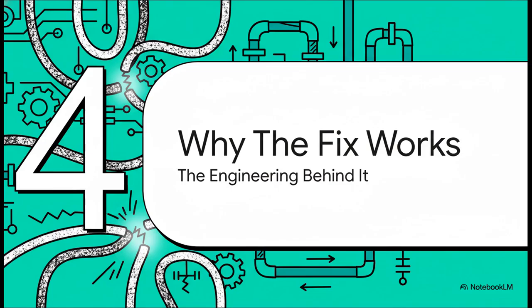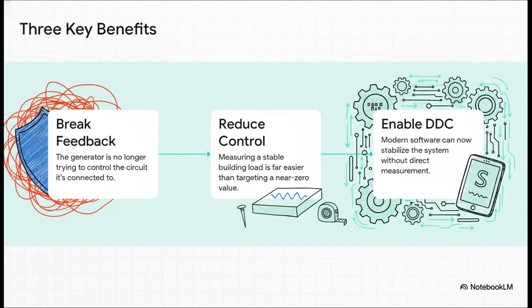So let's break down why moving a little sensor has such a massive impact. This one simple change gives you three huge benefits. First, and this is the big one, it breaks that chaotic feedback loop. The generator is now listening to a stable signal, the building's total demand, not the twitchy signal at the meter that it was causing itself.